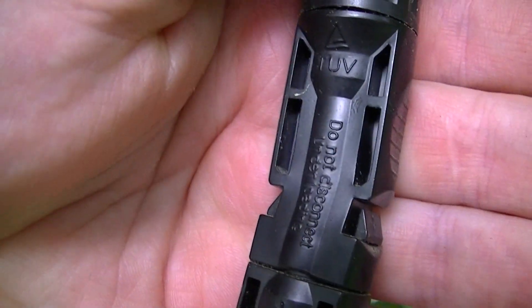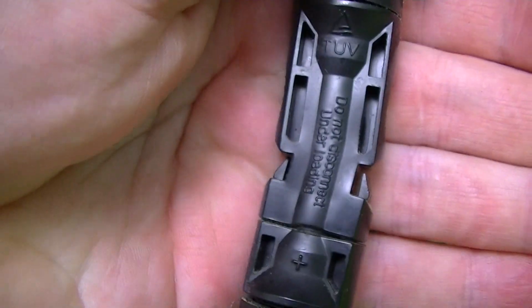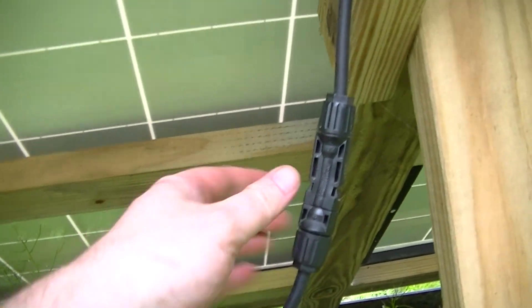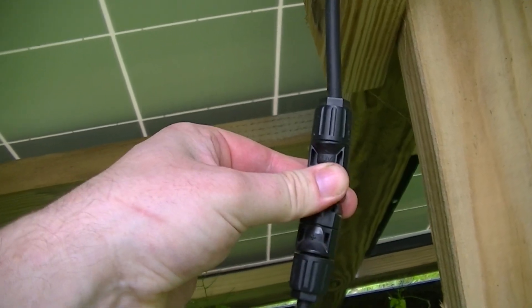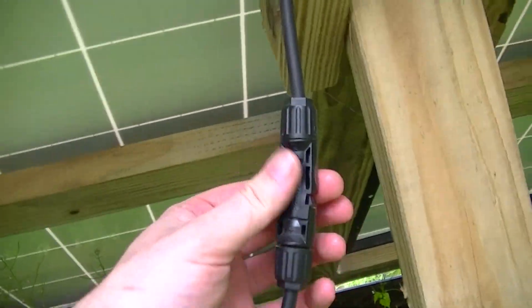As part of my inspection 10 minutes ago when I was back here, I saw this. It has warped, as you can see. So that's what the Mystical Bag of Magicalness is for, because I'm going to be cutting this defective connector out and replacing it. I don't want another one of these burning off because that already happened sometime last year.